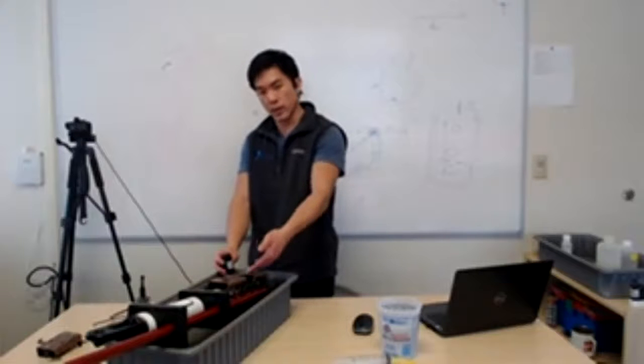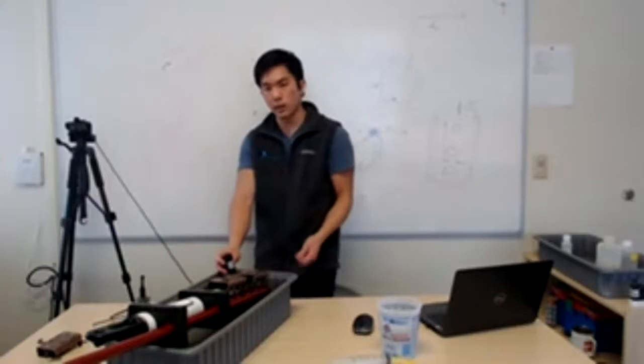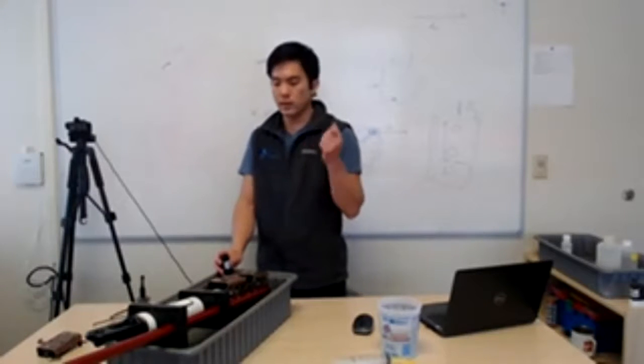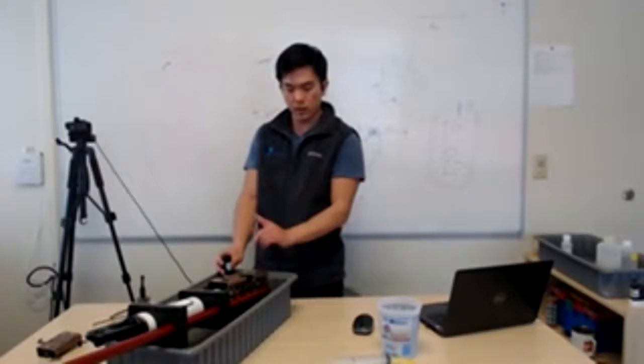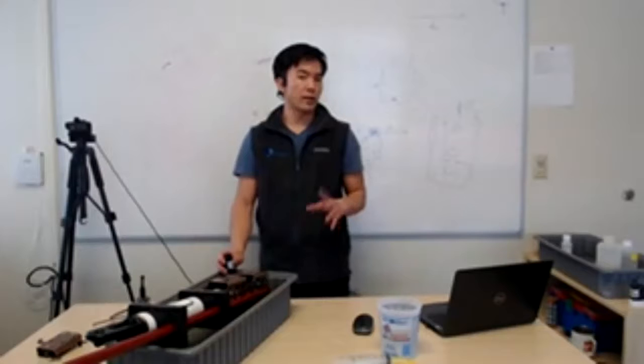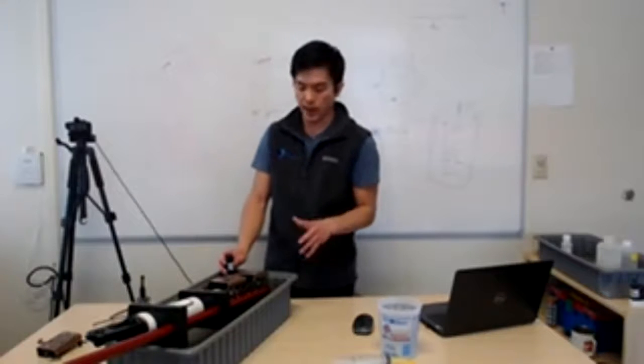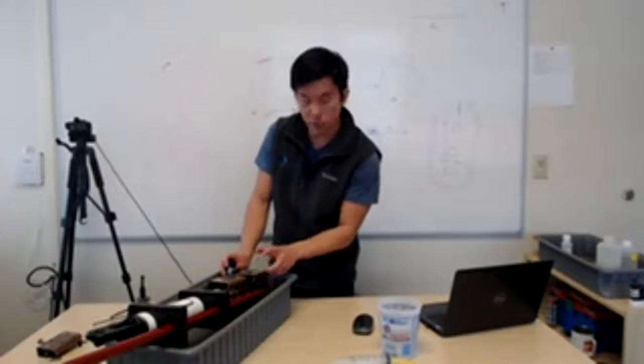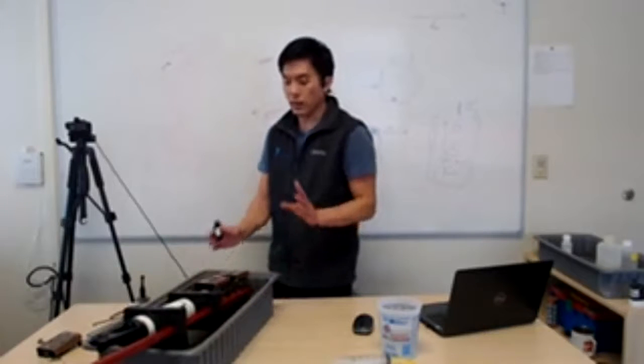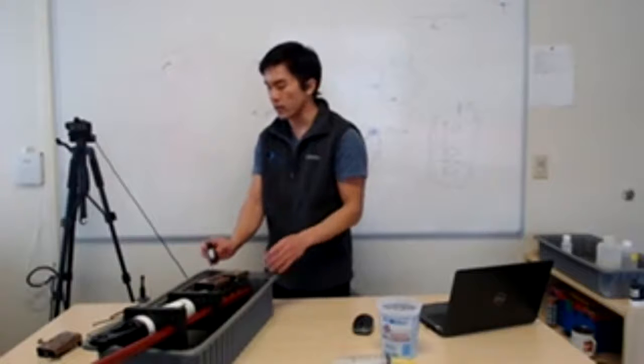I also want to make sure to inspect the connector inside of the HydroCAT EP. Take a lint-free wipe, like a Kim wipe, and dry out that area. If you have access to it, I also recommend taking a can of compressed air and spraying into the connector area just to get rid of any water. If you really want to make sure it's safe, you can also take high purity isopropyl alcohol and use that to displace any seawater on the instrument.